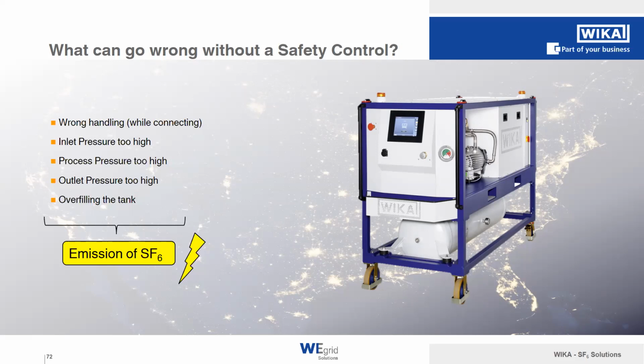And we could also have a process pressure which is too high, so a valve could no longer open, and the compressor is pushing the gas flow against the valve, which is not opening, building up pressure, and then the pressure has to be relieved over a safety valve. These signals from the non-functioning valve will be taken into account in our safety control, and it will be shown to you, so you are not going into that failure process.